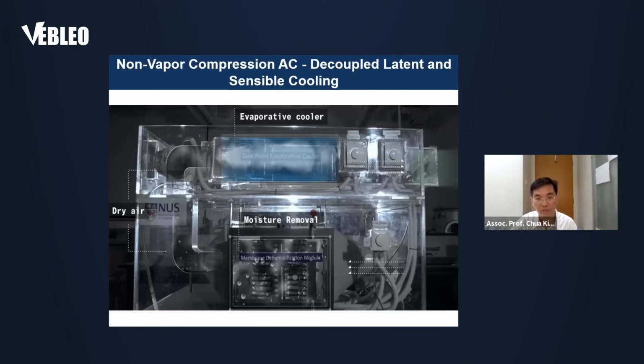The advantage is that it's more energy efficient, doesn't use chemical refrigerant, and doesn't reject heat to the environment. The 15% of air mentioned earlier is thrown out to the environment, but because it passes through the water layer, the air that comes out is typically at the wet bulb temperature of the water or air, about 26 to 27 degrees.